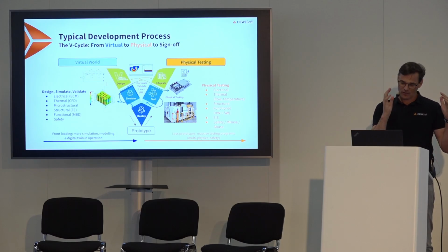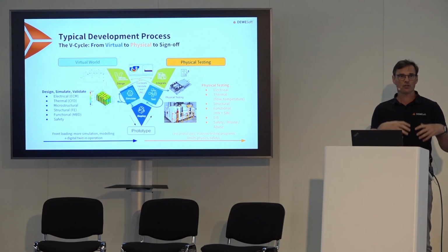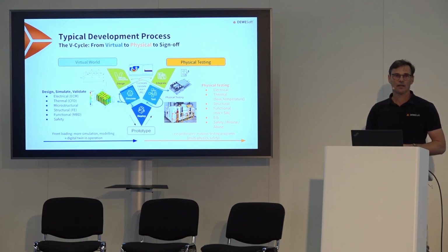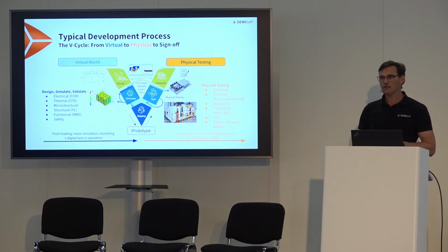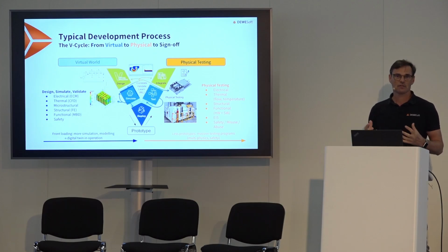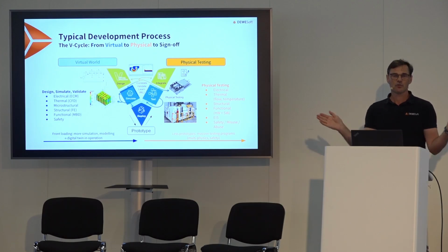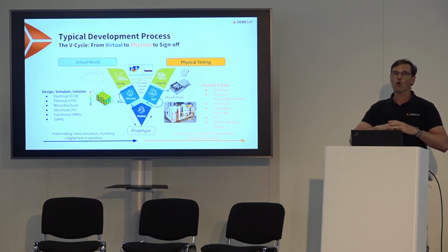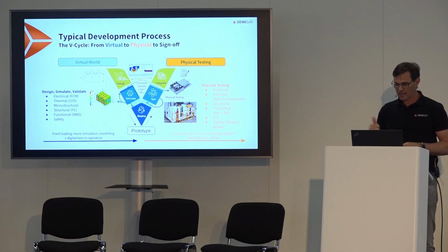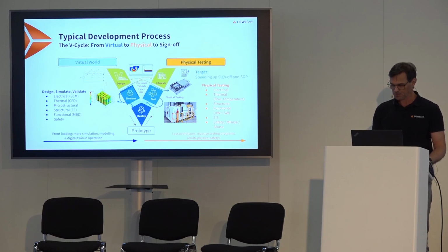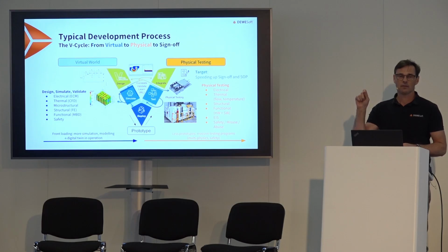What we see is front loading means more simulation, more modeling towards a digital twin in operation. And in the physical testing world, we see fewer prototypes. Not like in the old times with 100 prototypes—now you only have a few, hand-selected, and these go through all domain testing: electrical cycling, durability, and at the very end, the short circuit test. So fewer prototypes, but a massive test program and a lot of multi-physics needs, all towards the target of sign-off of the battery pack and start of production.